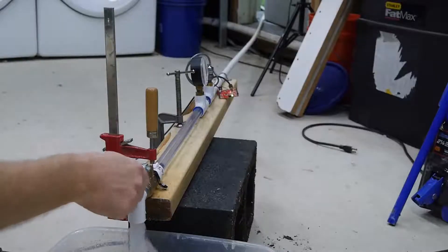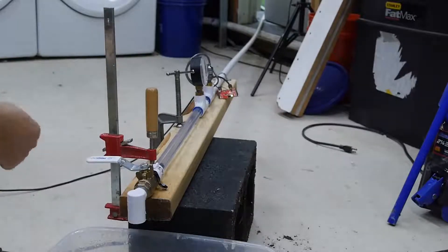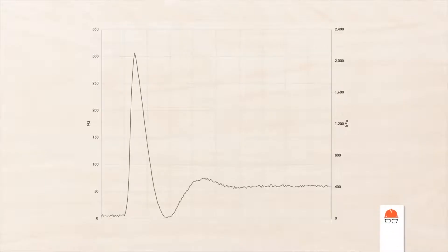Watch what happens when I close this valve. It doesn't look like much from the outside, but look at the data from the pressure gauge. The pressure spikes to over 2,000 kilopascals, or about 300 psi.